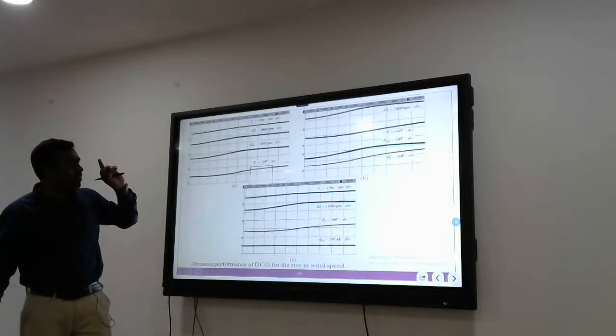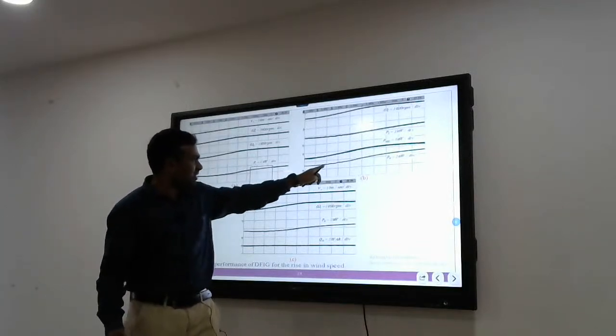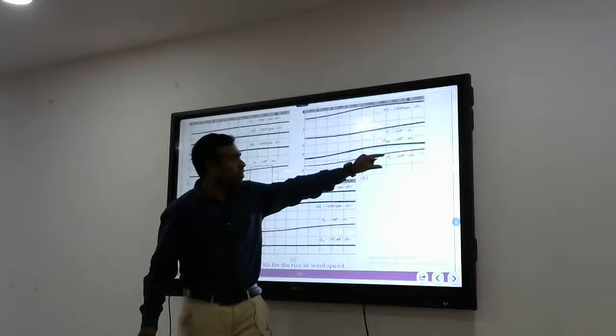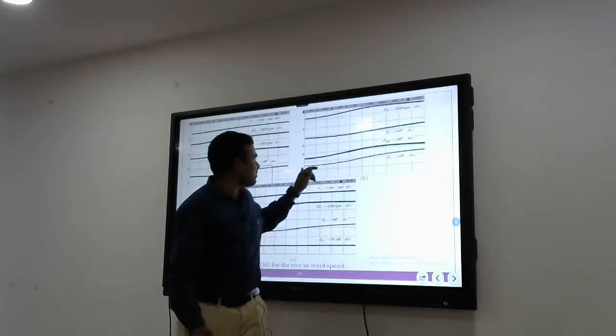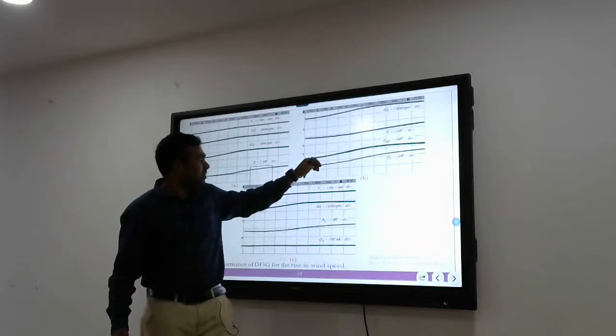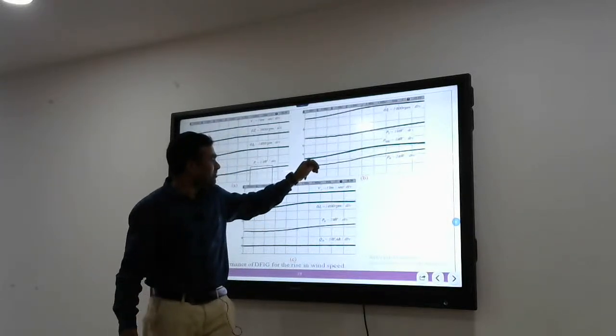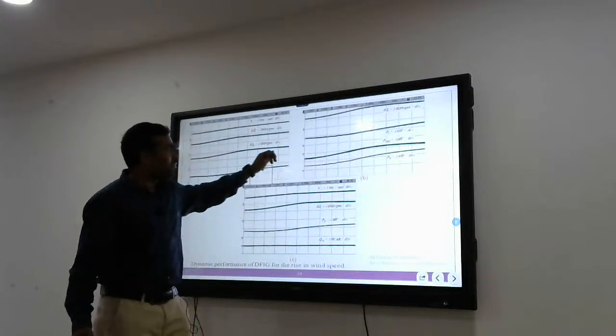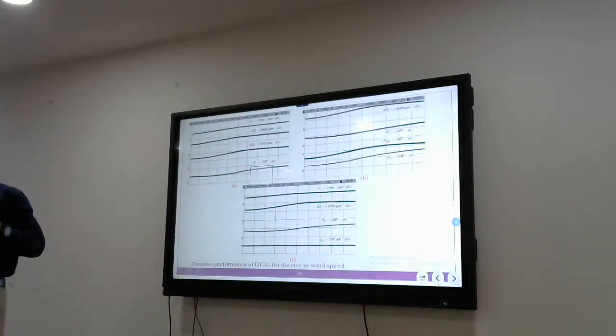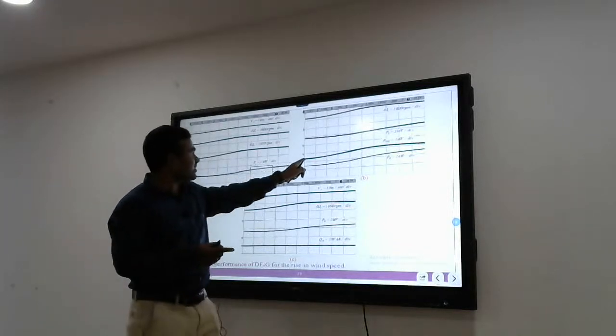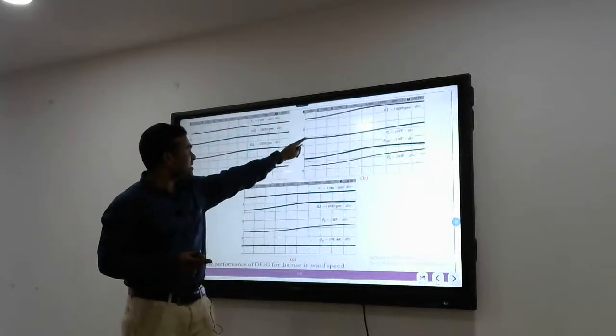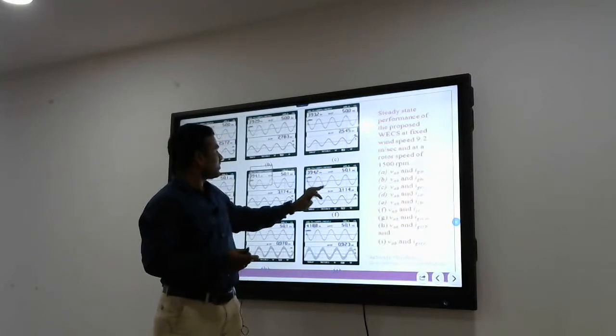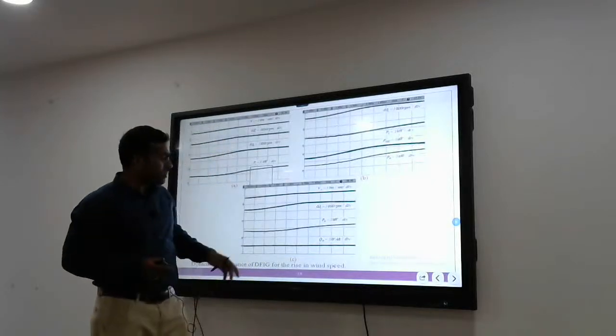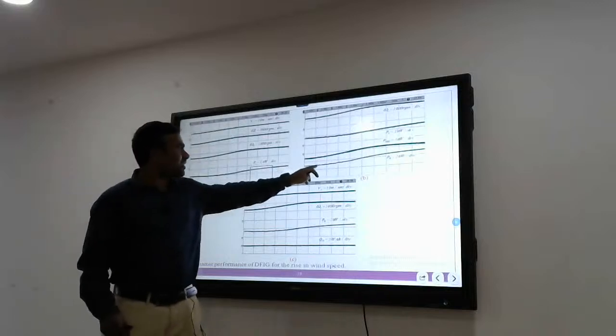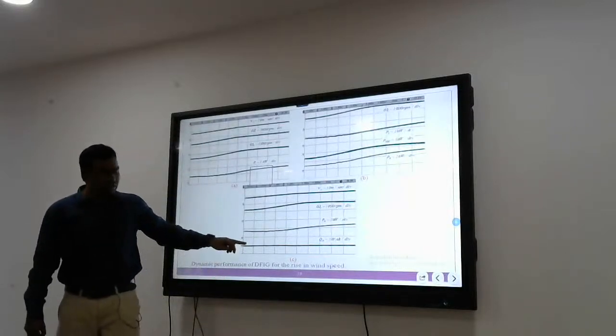So the power that is feeding to the grid, this grid power, is also increasing. Each division is 2 kilowatt, so around 3 kilowatt power is feeding to the grid. And this is the grid side converter, the power is changing its direction. Previously this is negative, now the grid side converter power is becoming positive. With the change in wind speed, suppose you are going from below synchronous speed to above synchronous speed, the power in the grid side converter reverses. This is stator power and grid power. Grid power is increasing and reactive power is 0.